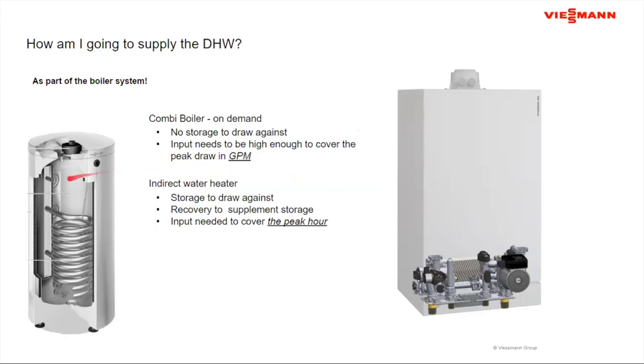When I do an indirect storage tank, I have a volume of water to draw against, but I also have a heat input from the boiler as well. So recovery supplements storage, and I can look at it as a combined output of that water heating method. Typically, because of the combined method of recovery and storage, when you size storage type water heaters for residential applications, it's about covering the peak hour. So here I'm looking at how much water I need per hour. Over here, I'm typically looking at the peak amount of energy I need per minute. In our discussion, we're going to first look at the sizing process, and I'm going to start with the combi boiler because it really is cut and dry compared to the storage water heater.